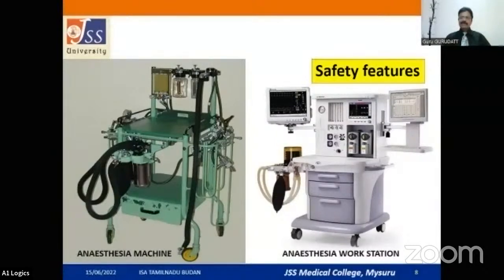These safety features have been introduced into the anesthesia workstation mainly to prevent a hypoxic mixture being delivered to the patient. With the older anesthesia machines, there used to be many mishaps of providing a hypoxic mixture to the patient, and many deaths have even occurred because of problems with these older machines. Now it is said that almost 99% of the time you will not be able to provide any kind of hypoxic mixture to the patient using the anesthesia workstation. They are absolutely very safe.